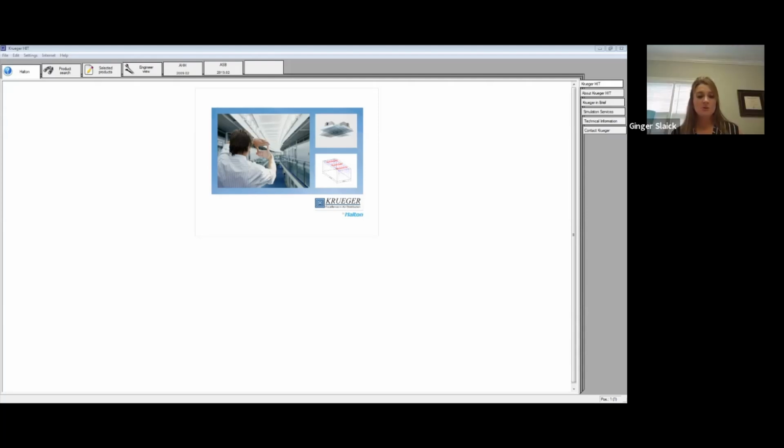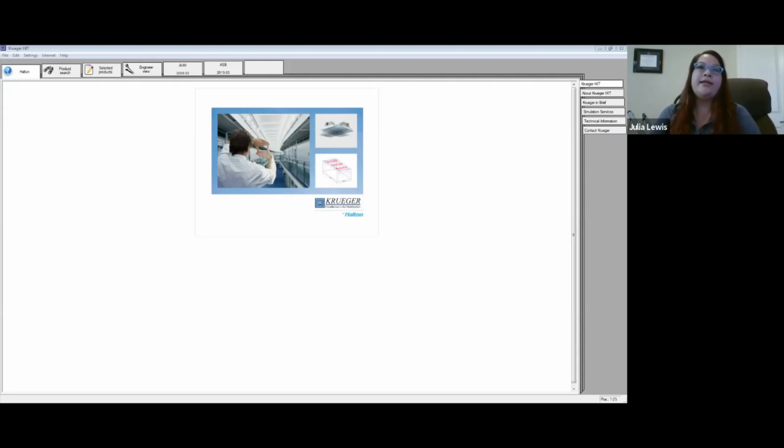Okay. The next question, are chilled beams used primarily in dry climates where humidity isn't an issue? Yes, these are definitely better in more controlled humidity kind of environments. These are actually pretty common in Europe, where they don't have as much traditional air or overhead air distribution. They've leaned heavily on the chilled beam in this process, it's a bit more new to North America. So it's not being designed as much in spaces here, and a lot of humid places are definitely shying away from it more because of the dew point being hard to, it's hard to not have them drip.